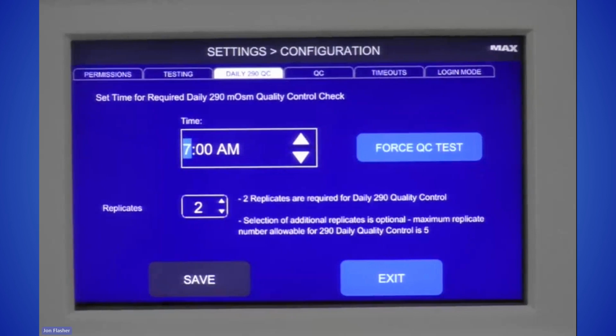As part of that, we put this feature in the software that allows you to schedule the time that you want to run your daily QC. Most laboratories, right, your techs will come in on first shift in the core lab, and they'll run a litany of quality control on a bunch of different instruments, usually around the same time of day. This gives you the opportunity to schedule the time of day that you want to perform the QC for this, so that each day it will require it at the same time.